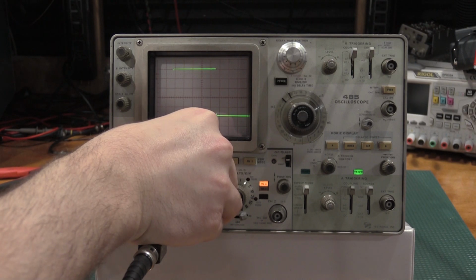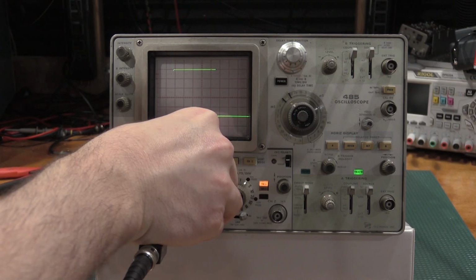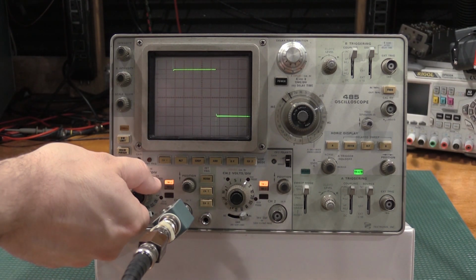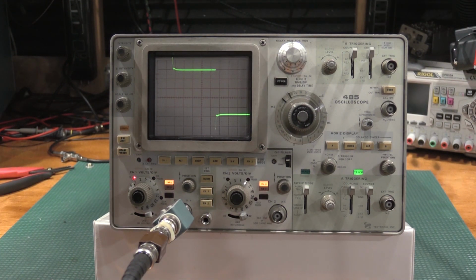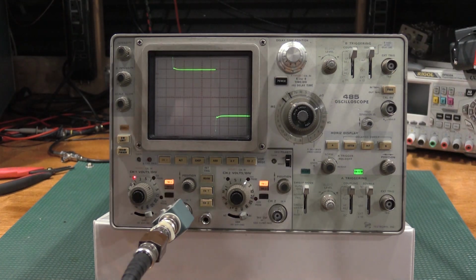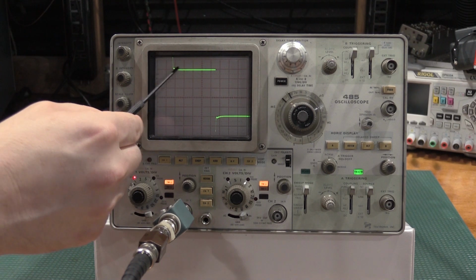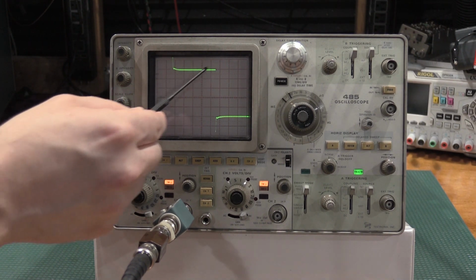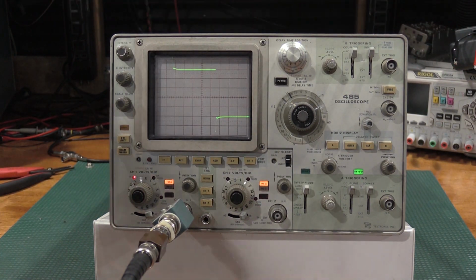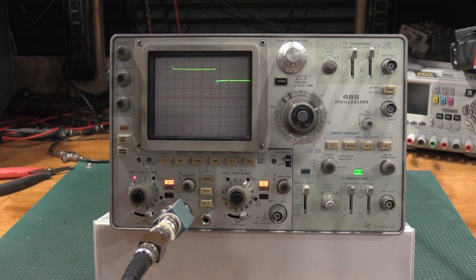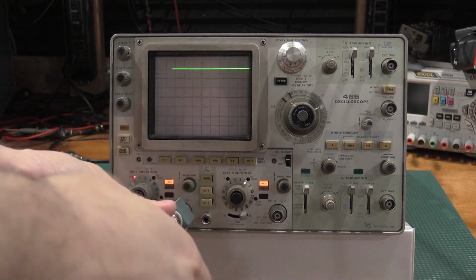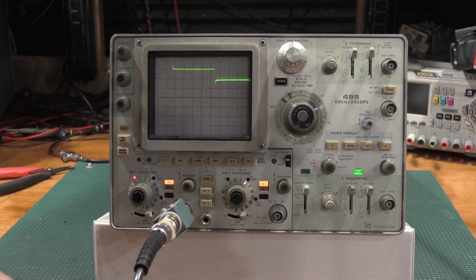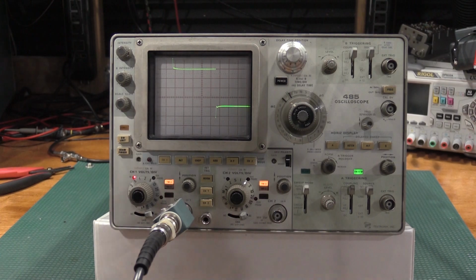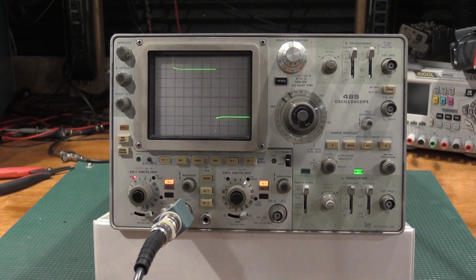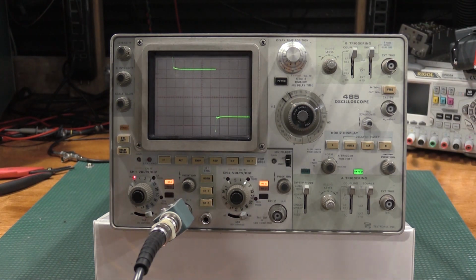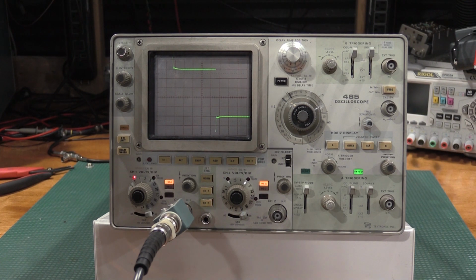Okay, checking channel 1's 50 millivolt. Looks good. 0.1. Also looks good. Now what I'm looking for is the best flat top out back. Up here we're going to adjust in a minute, so I'm not too concerned about that. I just want to make sure it's not really curving up on me towards the back end. 0.5. Need to pull off that attenuator. A little bit more. Yeah, that looks pretty good too. Definitely going to need some stuff on the front end. All right, 1 volt.